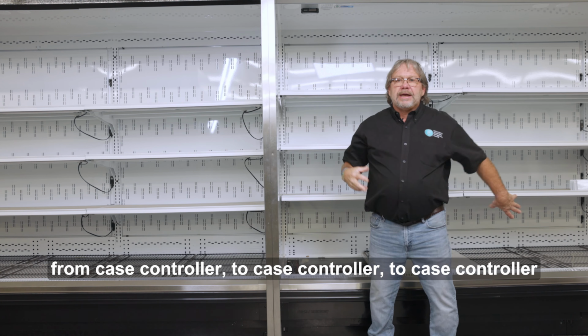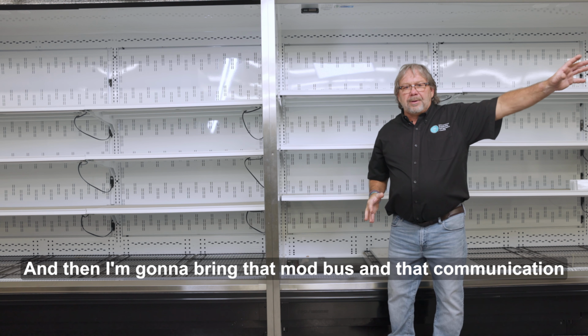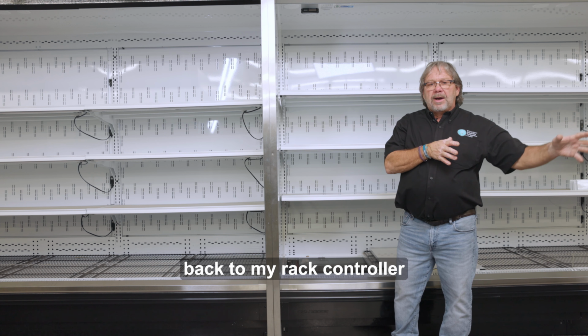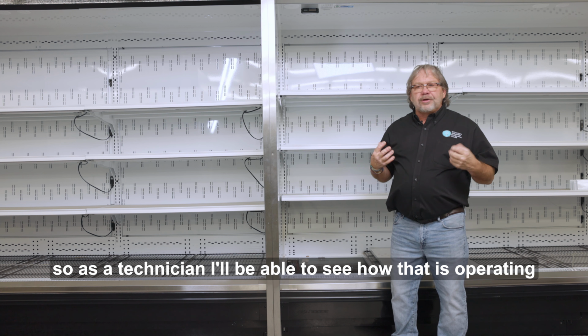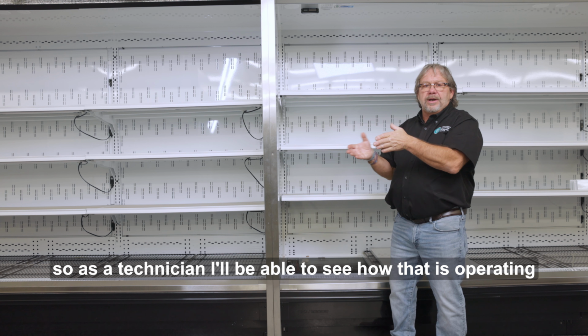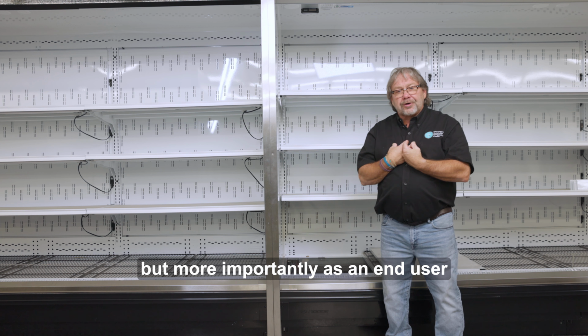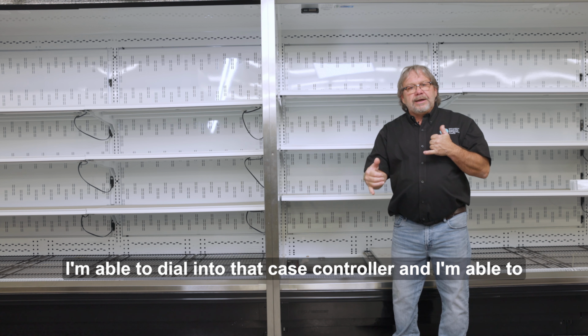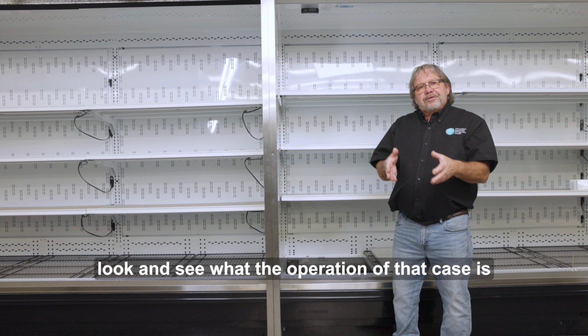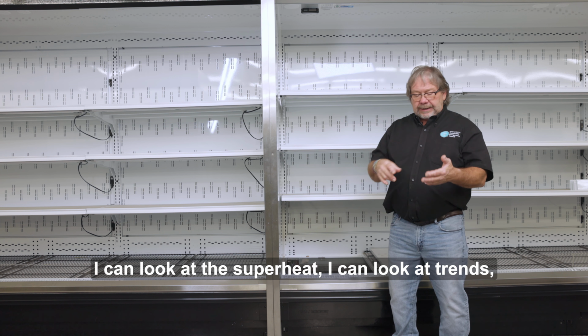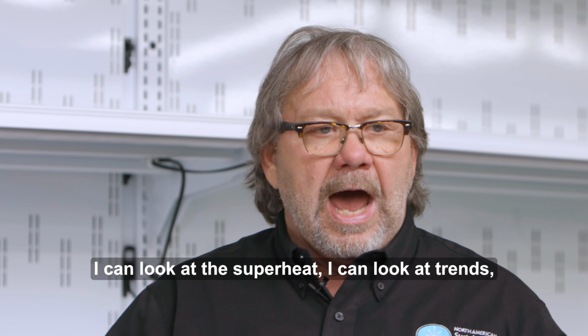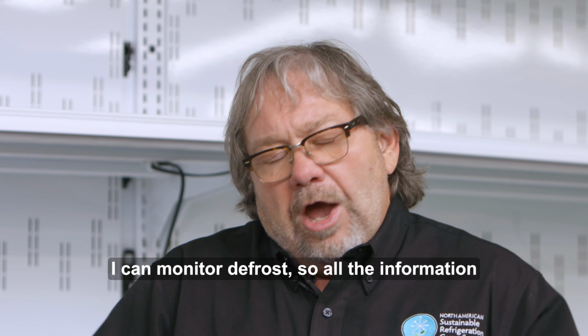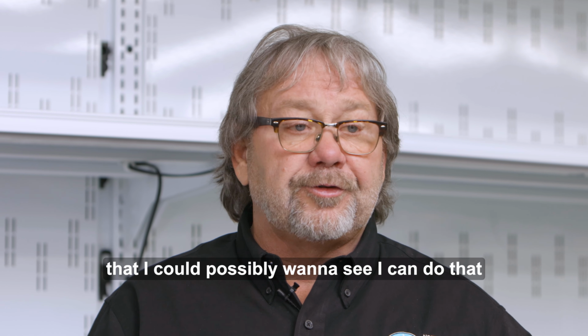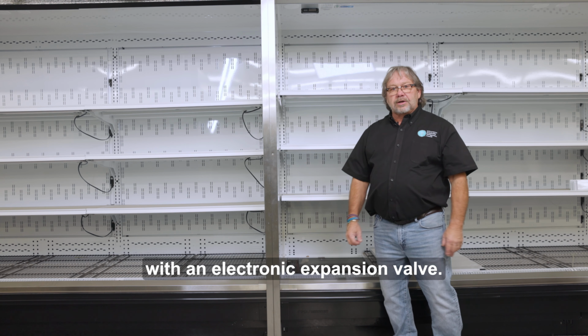Now, with the case controller, I do have to connect Modbus communications from case controller to case controller to case controller, and then I'm going to bring that Modbus and that communication back to my rack controller, so as a technician I'll be able to see how that is operating, but more importantly as an end user, I'm able to dial into that case controller and look and see what the operation of that case is. I can look at the superheat, I can look at trends, I can monitor defrost. So all the information that I could possibly want to see, I can do that with an electronic expansion valve.